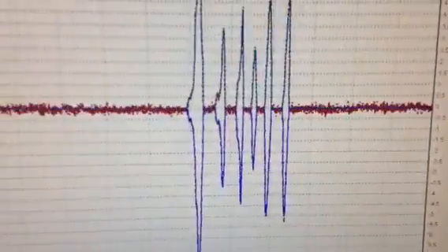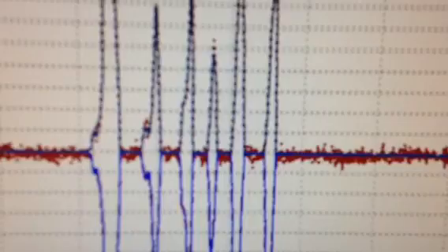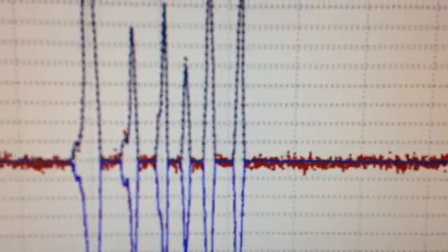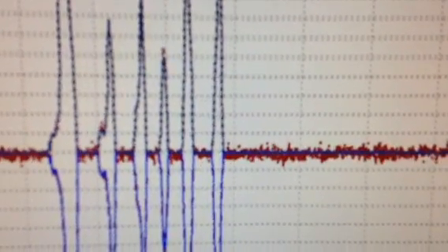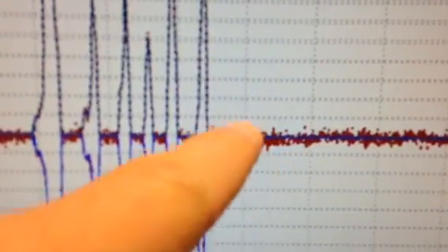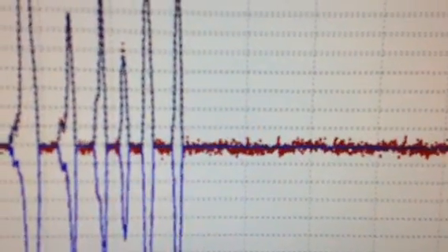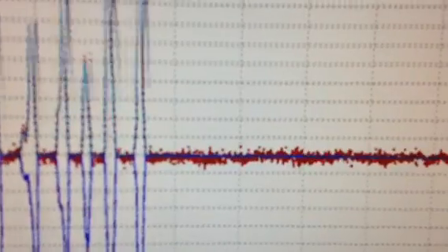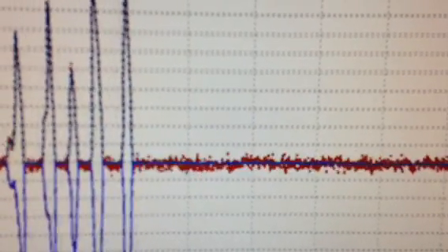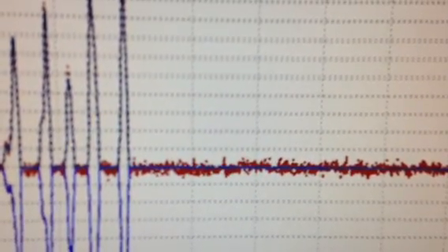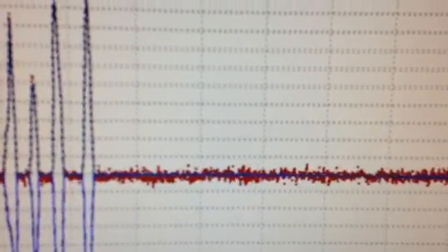And if we zoom in on that, what we see is that the vibrating wire data is very consistent and very solid, and for the bonded foil data, the mean is useful, but there's a lot more spread in the data.